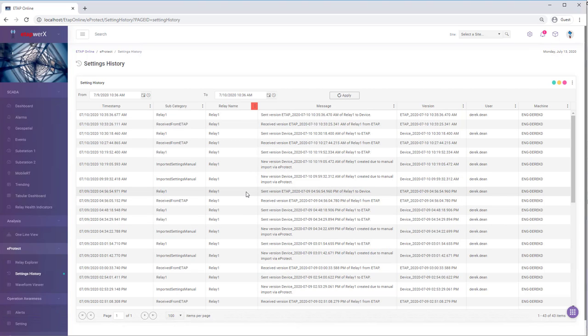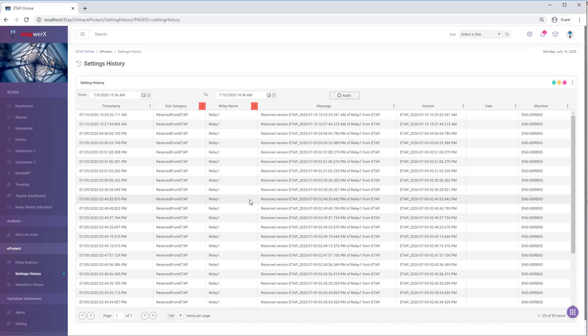So if we wanted to filter by the most recent work we did for Relay 1, we can filter by the relay name, and we can also filter by the subcategory. This allows me to see how often these settings have been changed from an ETAP protection and coordination study, as one example. But you can select from many different subcategories to filter out and manage the changes that have been done to the assets on the field.